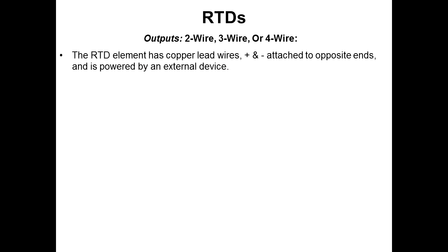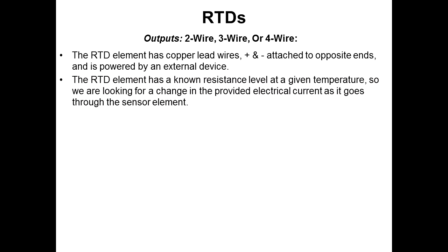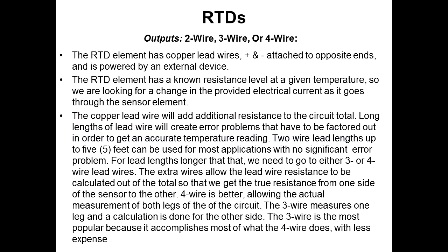So the RTD element has copper lead wires, positive and negative, attached to opposite ends of the element, and these are powered by the meter or an external device. This RTD element has a known resistance level at a given temperature, so we're looking for a change across that element from one side of the element to the other. The copper wire leading from the probe up through a handle or cable assembly on a handheld probe or being transmitted will add significantly to the error if you run long lead wires. On a 2-wire, you can go up to about 5 feet in length for most applications with no significant error unless you're trying to have a precision reading. For long lead wires, you need to go to either 3 or 4 wire.